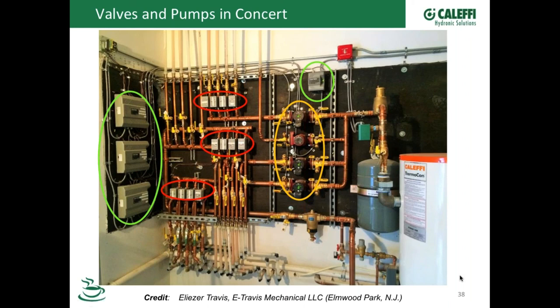Anything else on that, Cody? No, I was going to say I used to speak with Izzy on a fairly regular basis. I haven't heard from him in a while, but yeah, we found this on Heating Help, and it's just a perfect example. One thing that we didn't mention before, we've got all of our zone pump controls and zone valve controls. Up at the very top there, we do have a single zone control. That one's operating that single pump, that non-variable speed circulator there, the second one from the top, to kind of round out our lineup of controls.